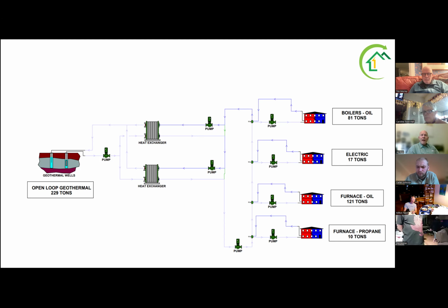I don't know if they have, while Carter looks - I see him furrowing his brow. But I would estimate there is not a lot of load diversity there. You would have periodic times of pretty good, during swing seasons when you're switching from summer to winter and winter to summer, some buildings may be air conditioning at the same time as buildings are heating. That would be good load diversity, so you'd have snapshots of high COPs.